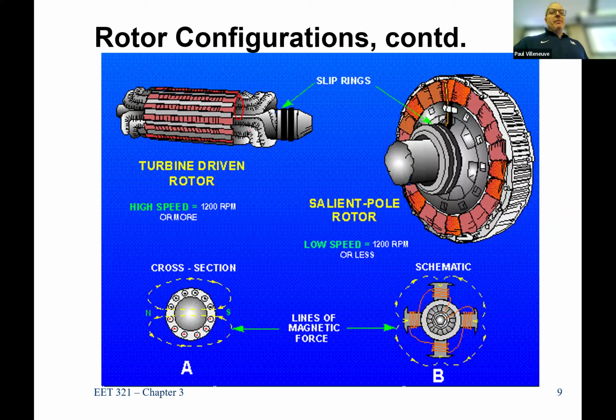So this is a high-speed application. This is the round rotor. Normally it's driven by a turbine. Turbines can run at 3,600 RPM really well. They can also run at 1800 RPM, okay. But anything less than that, you start getting into problems. So you'll find these at 1800 RPM and less. They're cheap to make and easy to do. But you'll see the magnetic field on a 2-pole machine, north-south. On a 4-pole machine, hard to tell, but you've got the north coming out here and the south returning back.